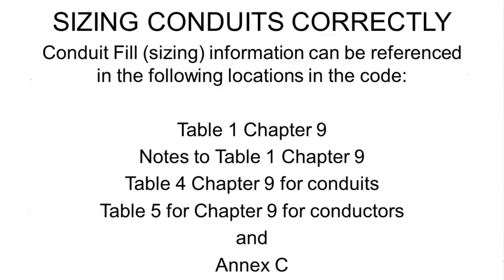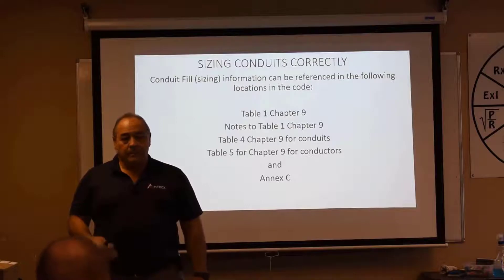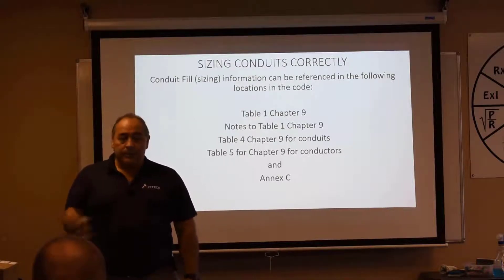Here's our layout of what we've got. We've got Table 1, Chapter 9 that gives us our information. We've got Notes to the Table, Chapter 9, Table 1. Then we've got Table 4 and 5. This is the interior size of the conduit and the exterior size of the conductors — how many can we physically fit? We've got Annex C, which is great if all the conductors are the same size and we've got the same conduit or raceway for the entire length.